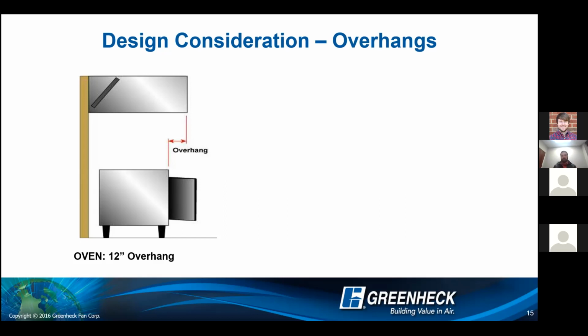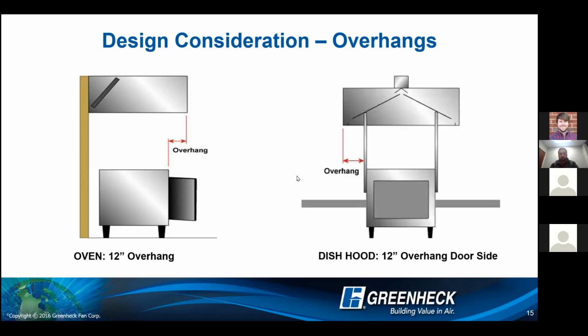So if you can, with ovens, I would design for a minimum of 12 inches of front overhang, and my personal recommendation would be 18 inches. Now, I understand we don't always have that type of ceiling space, but it's something for you guys to consider when doing your designs.